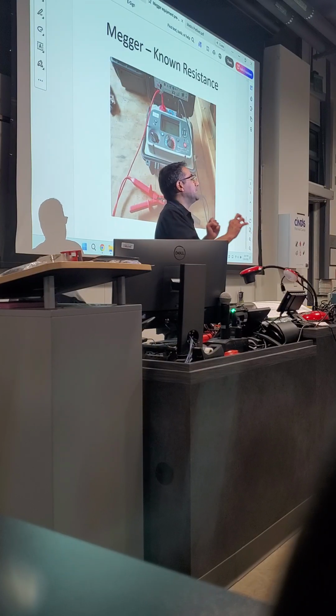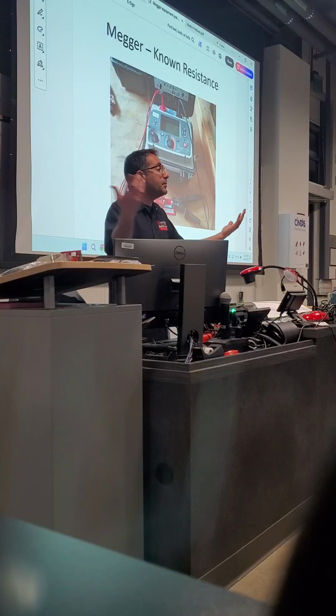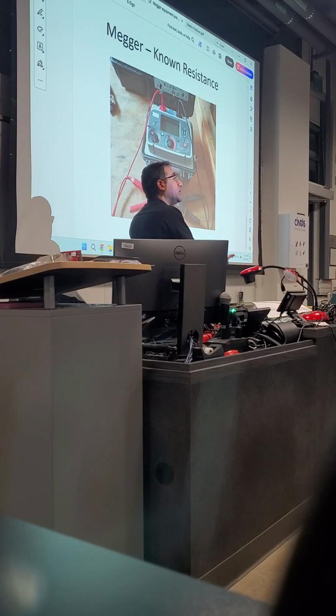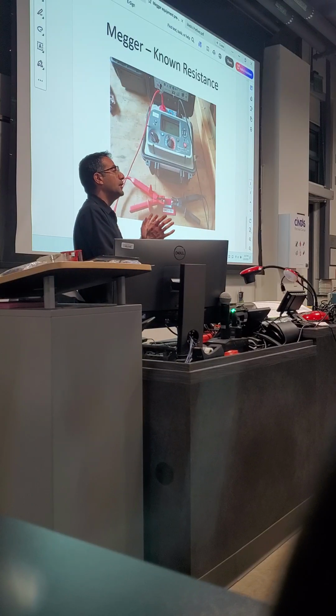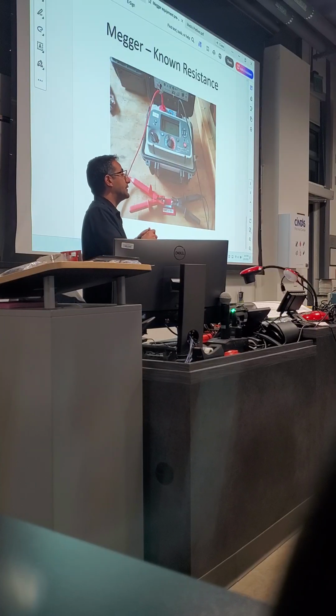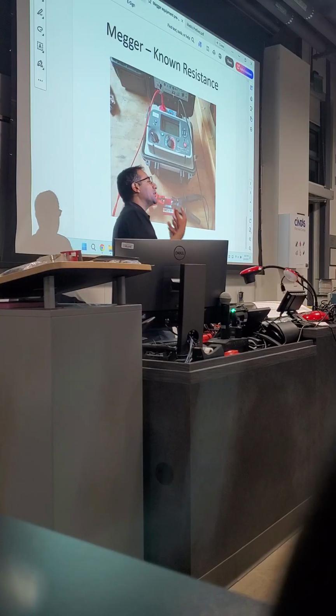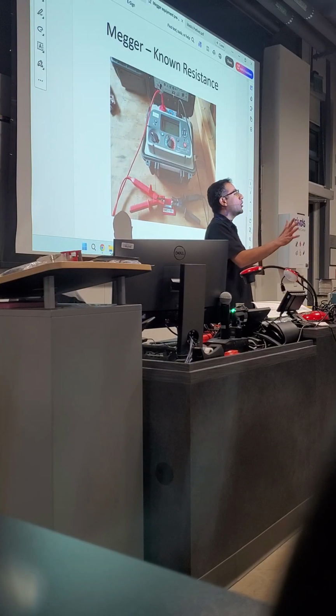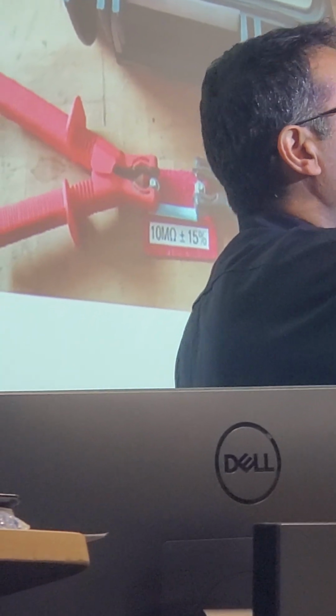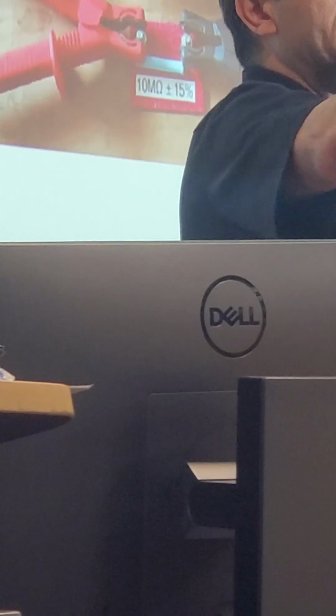But when you run the test, say it loud. Testing this way, you are letting the people around you know that they are exposed to the live voltage. No one is supposed to touch it. So say it loud, testing, because another person may not know when you start running the test. So when you say it loud, they're gonna become conscious about what's going on. They're not gonna touch anything until you finish the test. So let the people around you know that you are running the live voltage. And I'm gonna check your setup right before you run the test and work on that 1 minute timer as well.